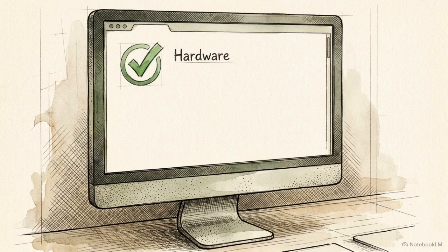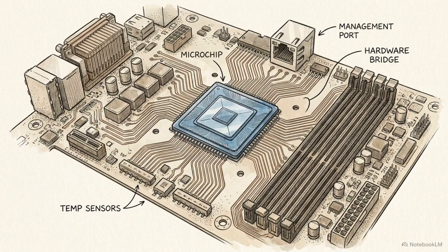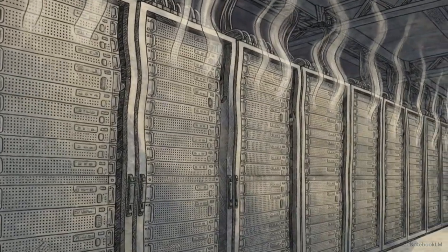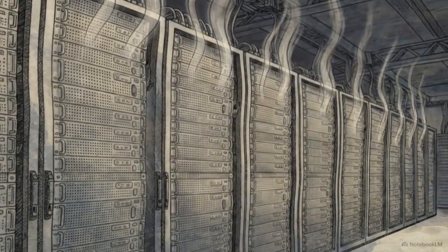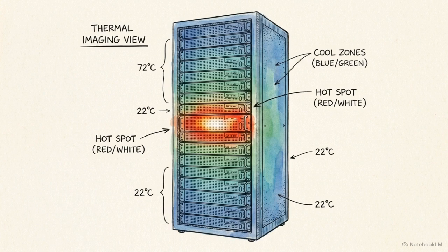Pulling basic health flags into an OS-based platform through custom forwarders is a common but insufficient workaround. It lacks the dense time series data needed for predictive analysis. The BMC serves as the mandatory complementary foundation, sitting squarely between the building's infrastructure and the application stack. This gap is becoming a critical failure point as AI workloads push hardware to its physical limits. Modern AI-optimized servers draw 10 times more power than prior generations, pushing rack density toward the 50 to 100 kilowatt range. At these densities, minor thermal anomalies quickly escalate into critical threats to the hardware.